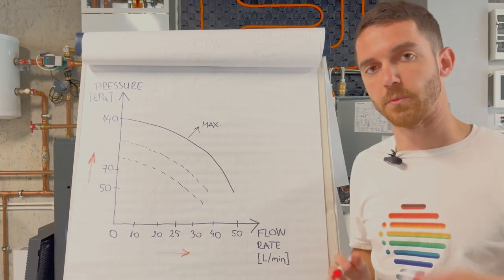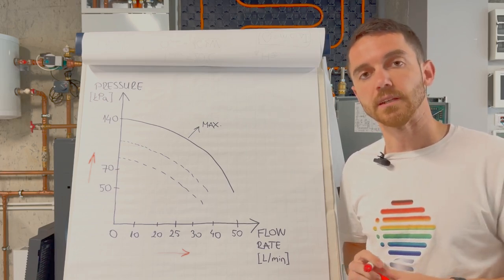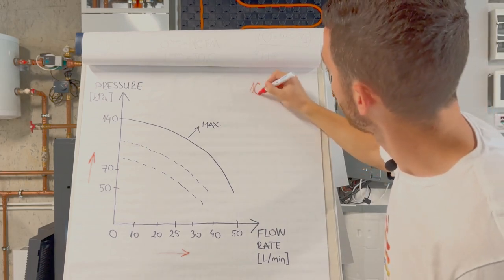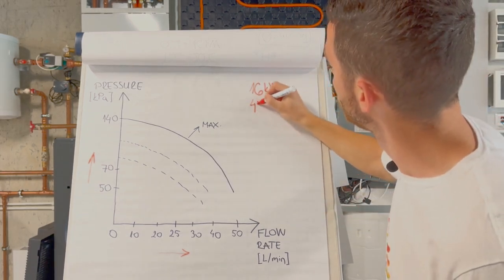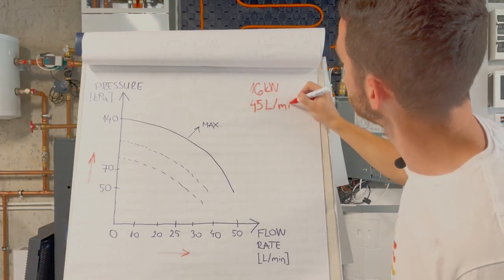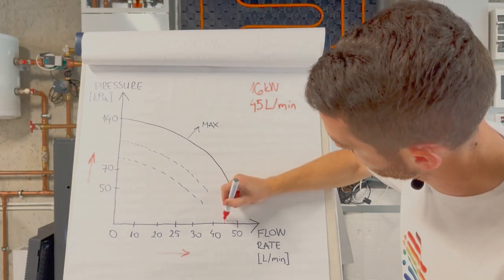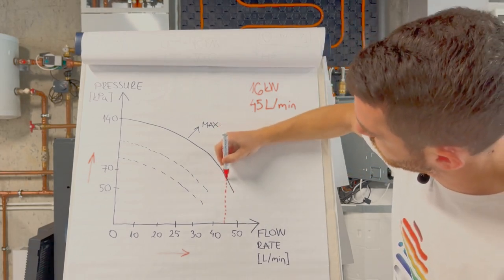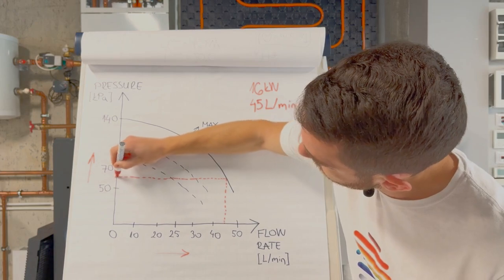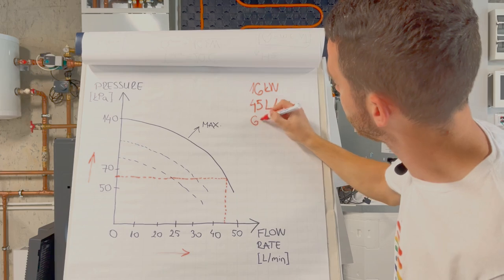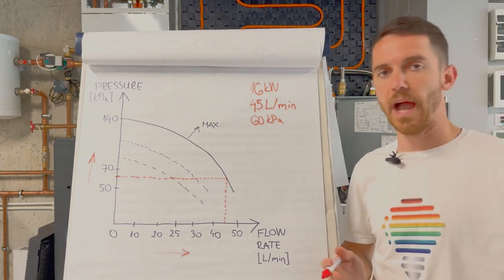What we will focus here, we will focus on the highest domestic hot water and heating heat pump, it's 16 kilowatts. And for 16 kilowatt our nominal flow rate is around 45 liters per minute. When we go here on 45 and maximum curve, we have something like this. So we have around 60 kilopascal available pressure drop.